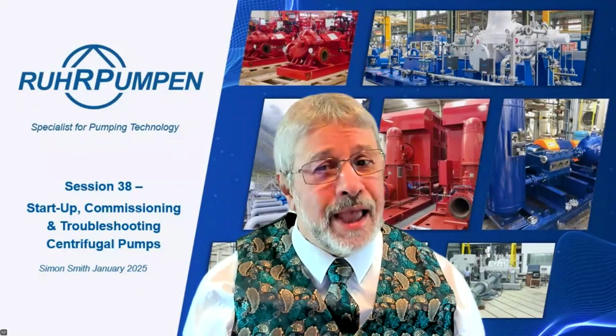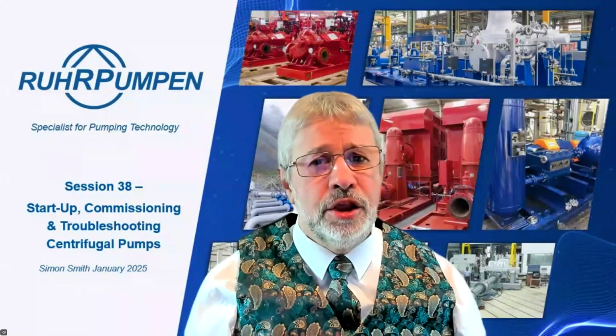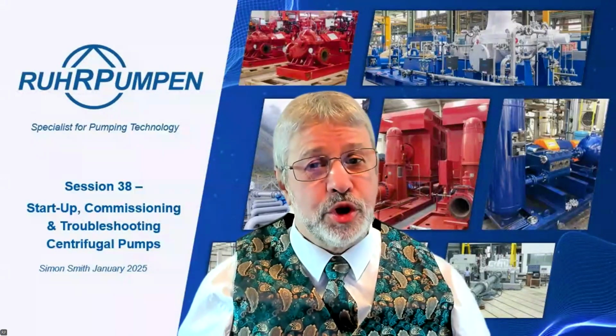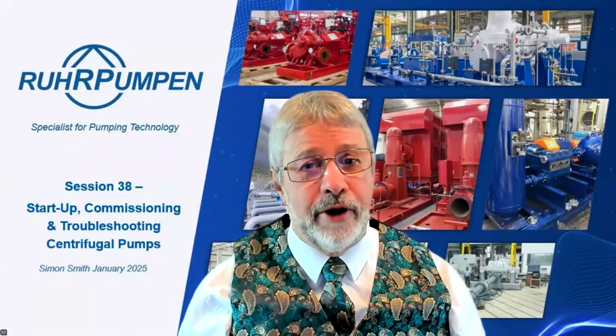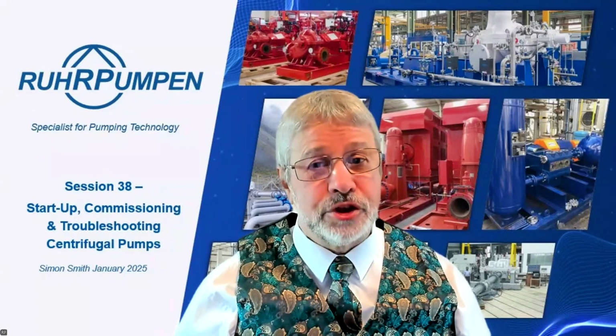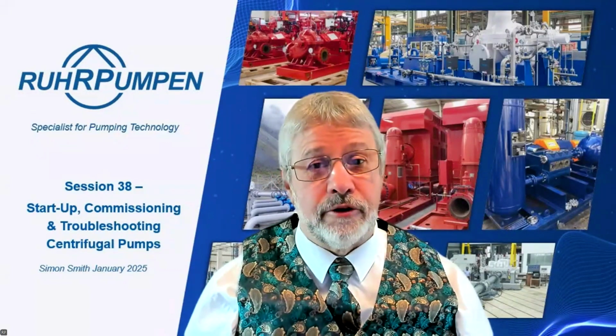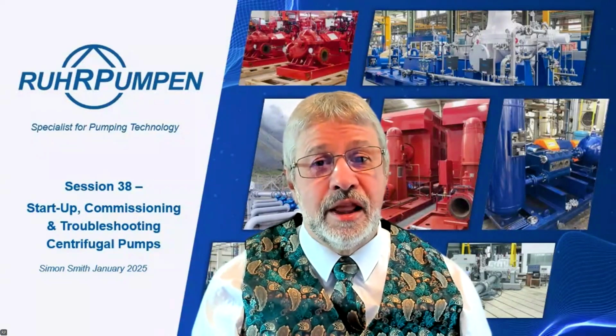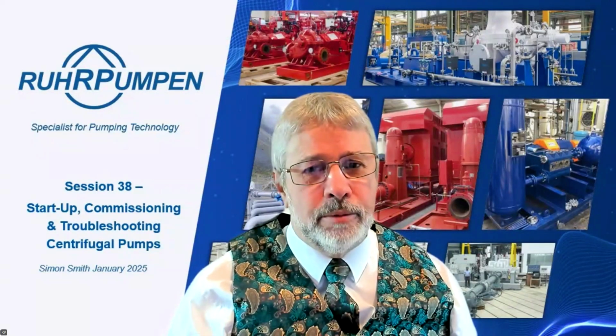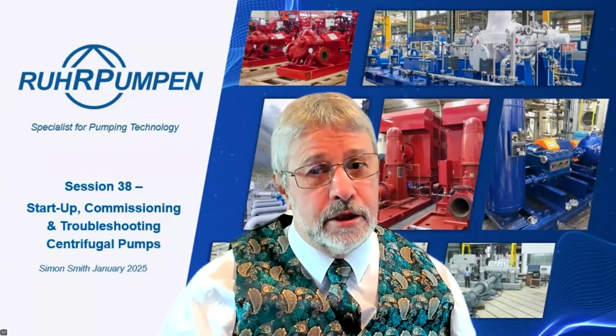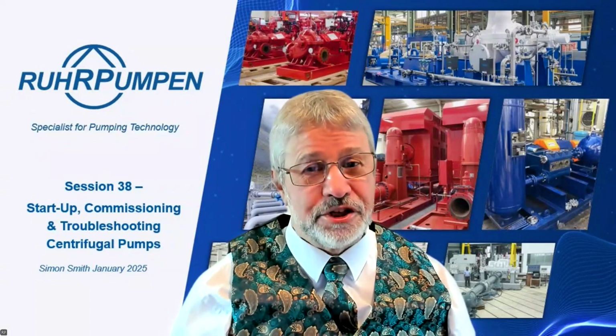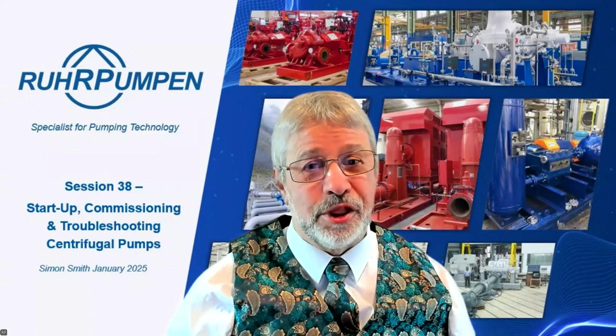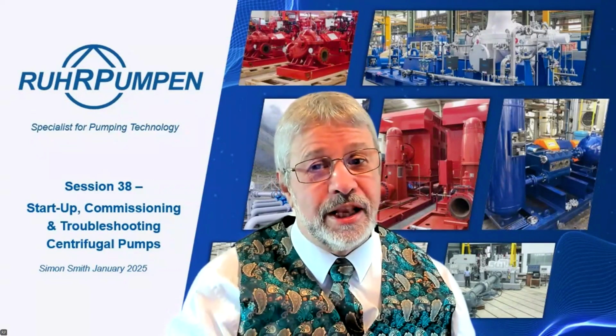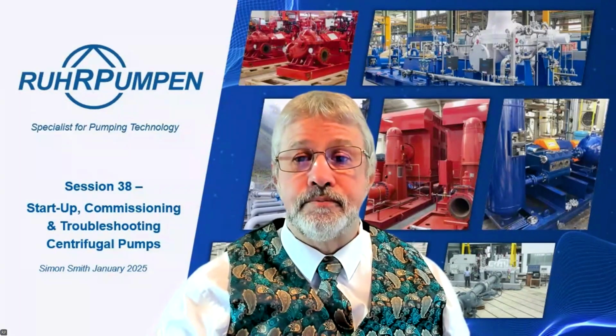Now, most mechanical seals are bidirectional. They don't mind which way they go, but some of them are unidirectional. And you have to make sure that they're going in the right direction. So you have to look at the mechanical seal first. What would be common on the mechanical seal would be for the pumping ring to be unidirectional, and then you need to make sure that you've got it the right way, or the pumping ring won't be circulating the fluid through the seal and seal system.